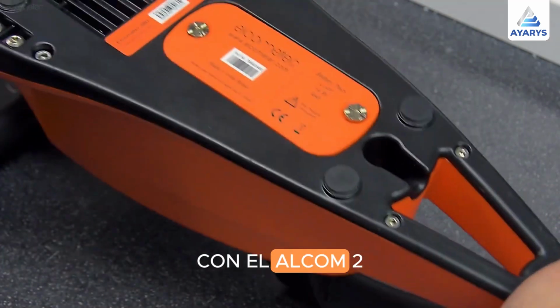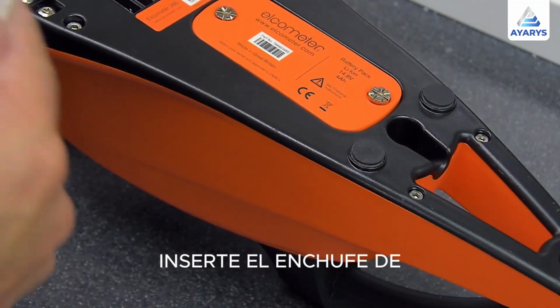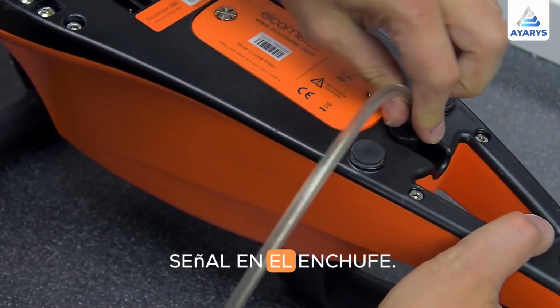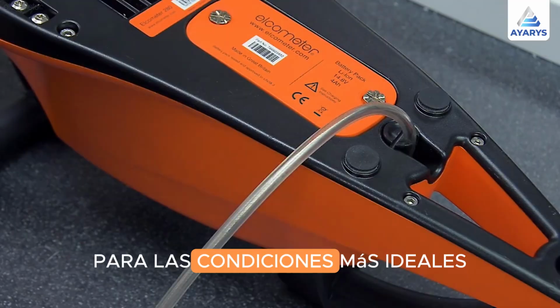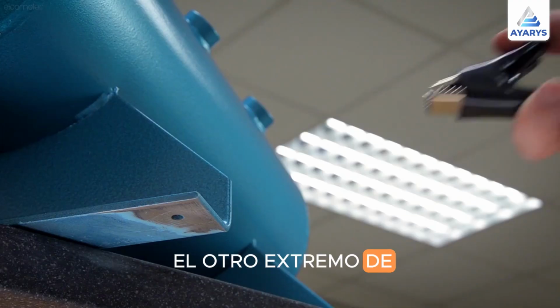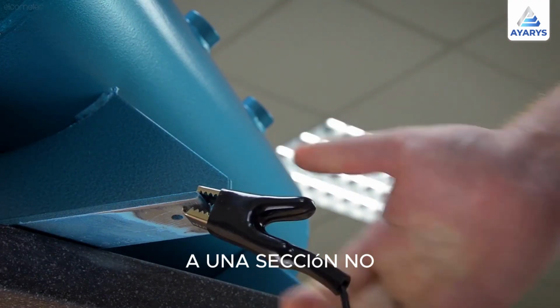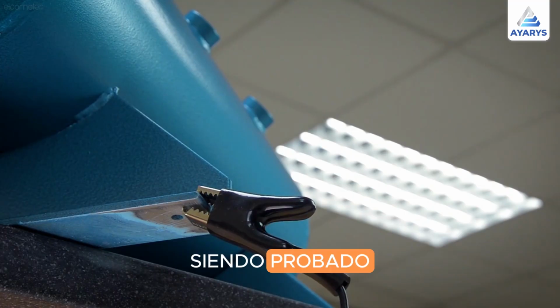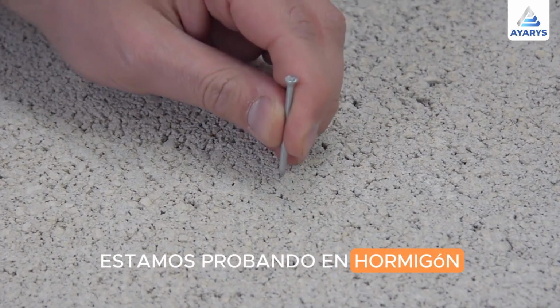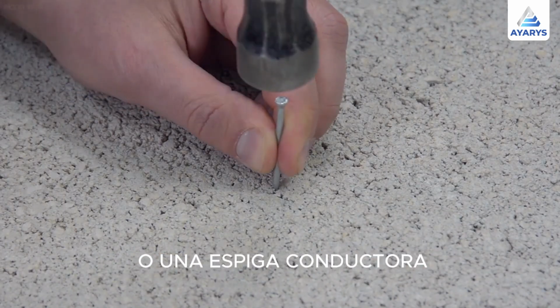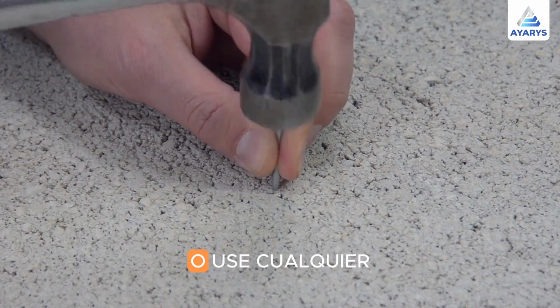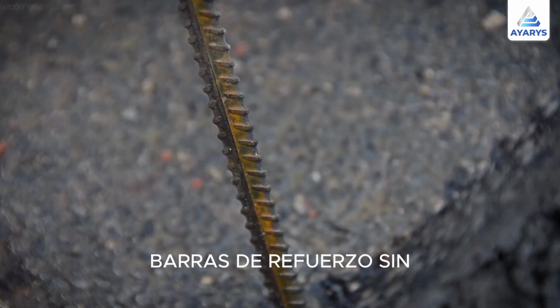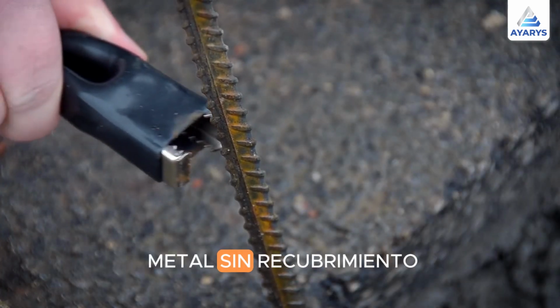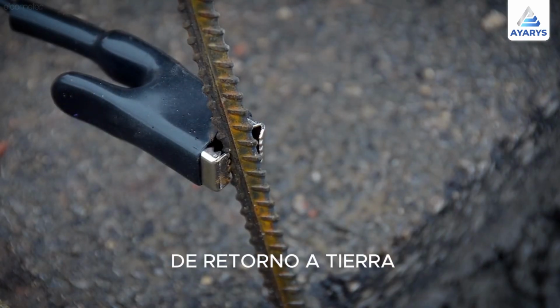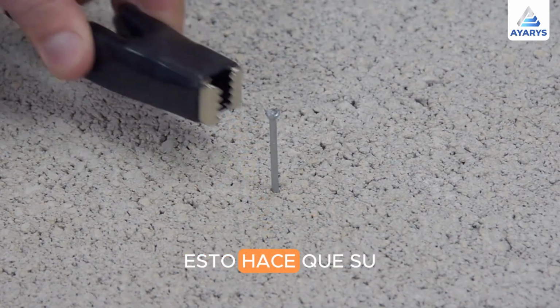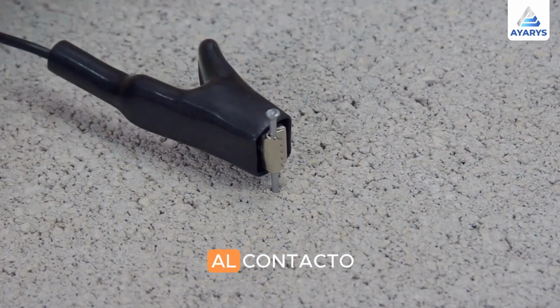With the Elcometer 280 switched off, insert the signal return lead plug into the socket. For the most ideal conditions, you should clip the other end of the earth return lead to an uncoated section of the substrate being tested. When testing on concrete, either hammer a masonry nail or conducting spike into the concrete, or use any exposed uncoated rebar or uncoated metal pipework, and connect the earth return cable to it. This makes your earth signal return contact.